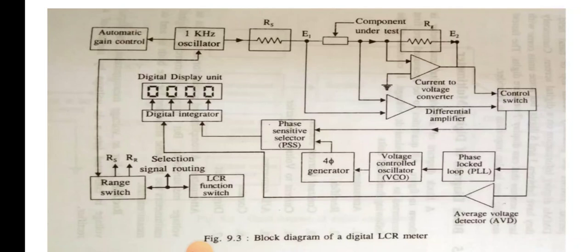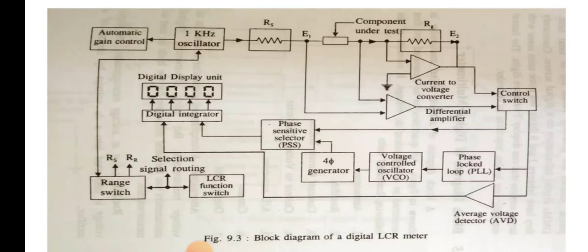In summary, the LCR function switch selects which parameter to measure. A one kilohertz oscillator with automatic gain control generates the test signal, which is applied to the component under test through resistor RS. A voltage E1, proportional to the applied voltage, is developed across the component.